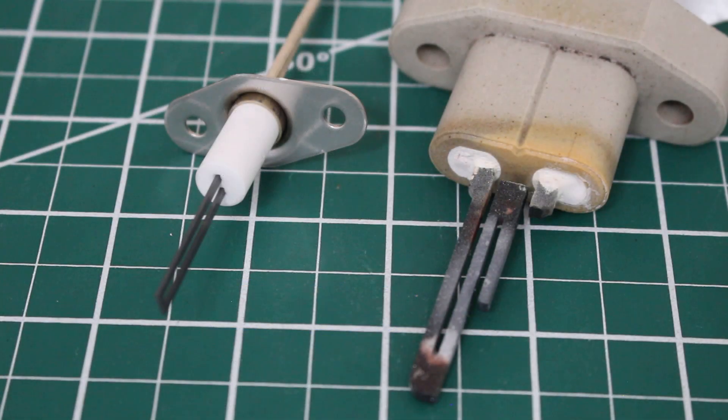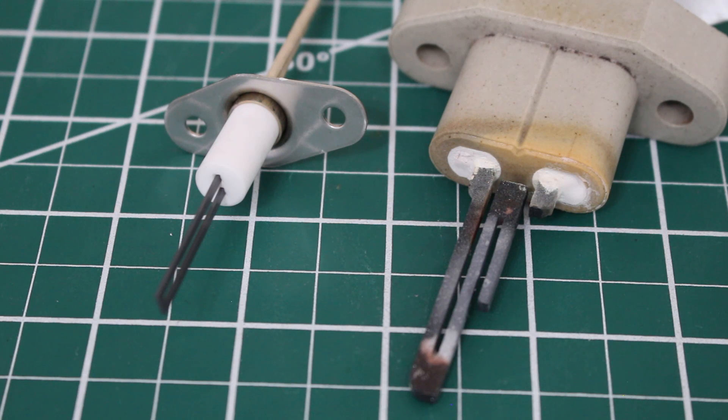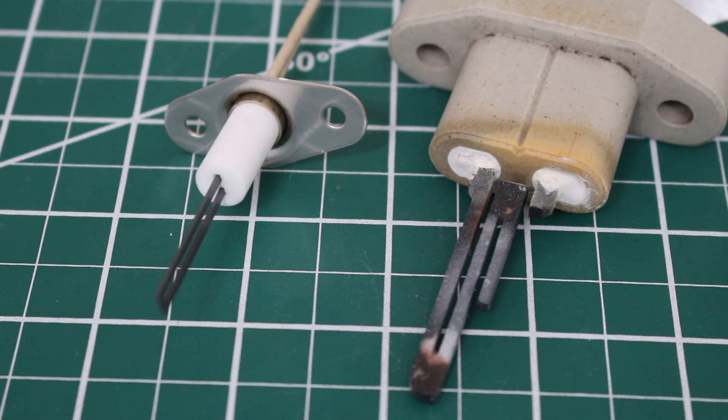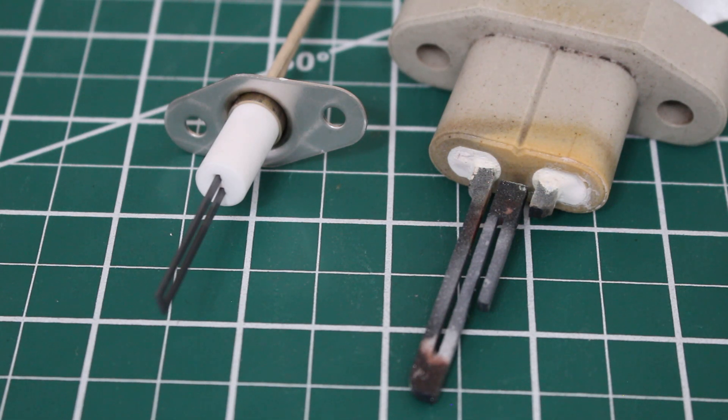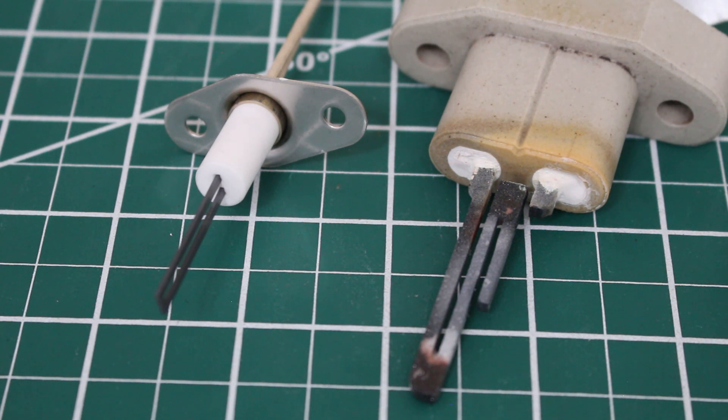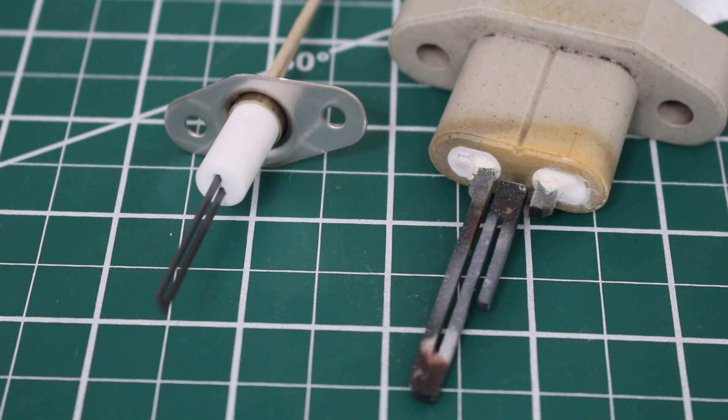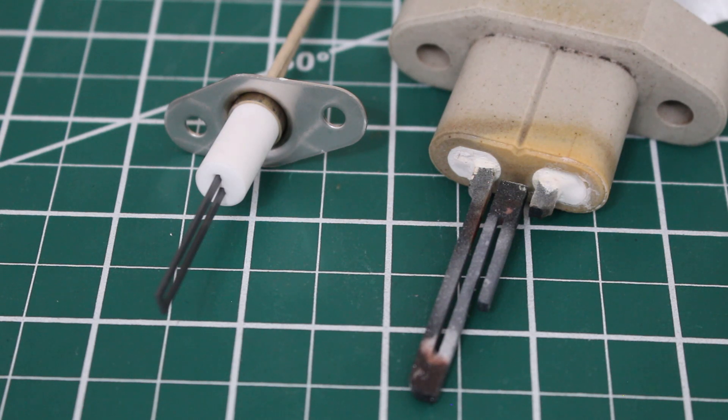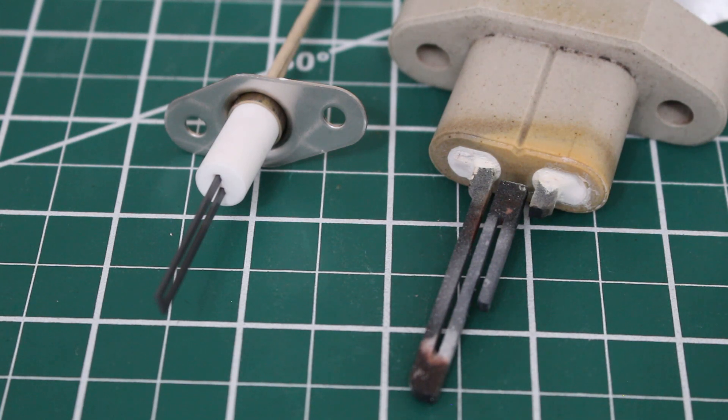Depending on the type of hot surface igniter you have it will give you a different ohm reading. Also temperature plays a role in this. As the temperature of the hot surface igniter is higher also the resistance will be higher. In this method I typically really don't advise it. I only use it as reference if I have an OL reading. In that case then we know what it is. But it's always important to check in with the manufacturer's ratings. Preferably the best way and the way that I do it is by checking voltage.